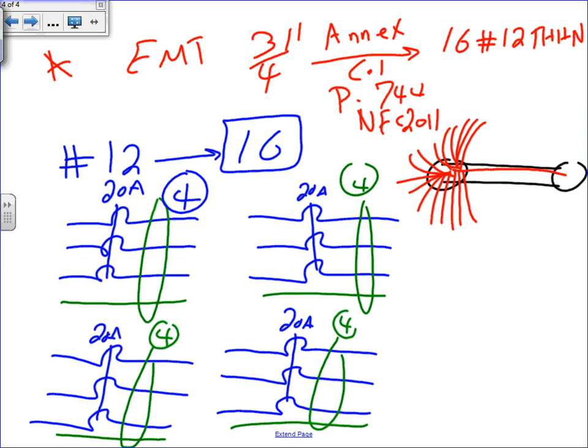Now can I put this in? These are all tied to single phase, one hot loads. Now, can I tie this one to a three-phase load? Not recommended. There are circumstances where you can, especially if the load is 208/120. Yes, then you can buy a three-pole circuit breaker: one big circuit breaker with three poles and one handle. It just trips all three of them. If the load is three-phase, most likely you're running with one circuit breaker, three-pole. That's typical, though I can use these under certain circumstances on a three-phase load.